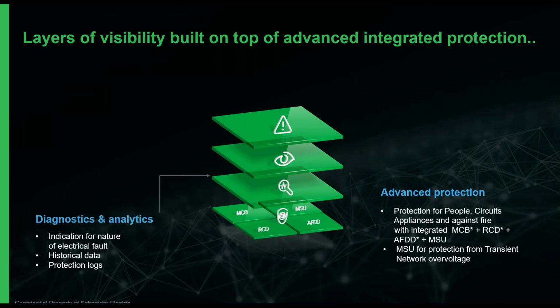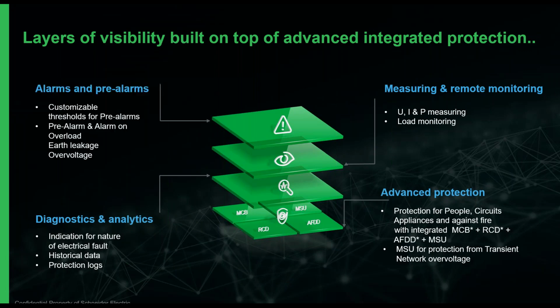In the next layer above, we get the diagnostics and analytics. This is where we can understand and have indications for the nature of the electrical fault. We get historical data, we get protection logs. Moving on to the third layer, we get measurement and remote monitoring. We can now see voltage, current, power. We can even get load monitoring. And then in the final layer, we get alarms and pre-alarms. Now we can have customizable thresholds for pre-alarms. We can have pre-alarms and alarms on overload, earth leakage, and overvoltage.